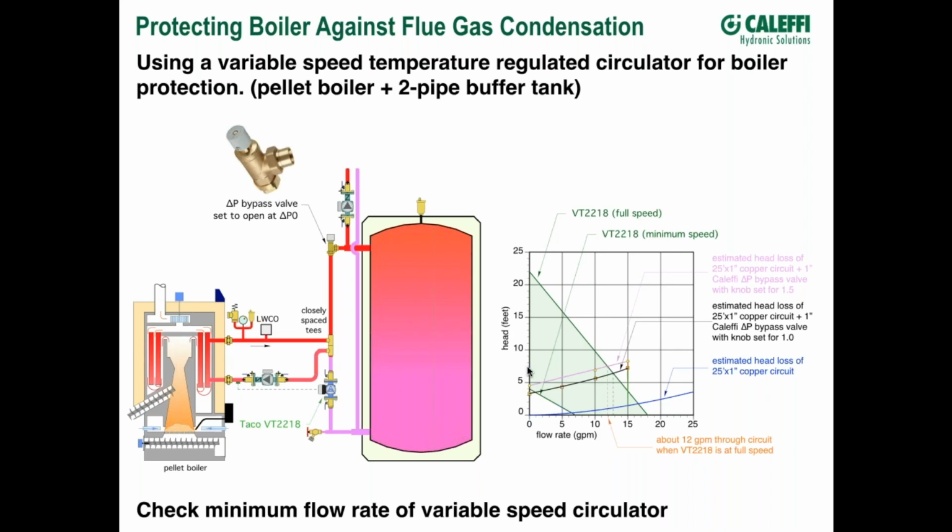The other thing that it does is it serves like a check valve. It prevents reverse thermosiphoning from the tank. Now, imagine we have this tank warm and we don't have any valve here at all, no check valve or delta P valve. What'll happen is the warm water will come out here, it'll start to cool, it'll descend, this pump would be off, and it'll just recirculate. This is called reverse thermosiphoning, and this will dissipate a fair amount of heat from that tank just sitting there. So we want to prevent that. And of course, the delta P valve has a spring in it that would close the disc against the seat whenever the pressure against the valve in the forward direction is less than 1 psi. So it takes the place of a check valve. So it's a nice little detail, and I do want to show that that detail can be scaled up.